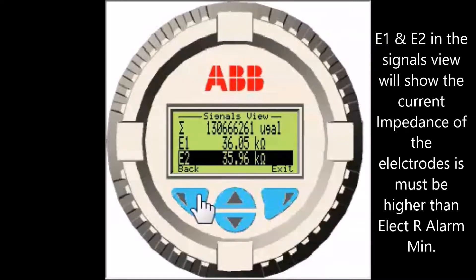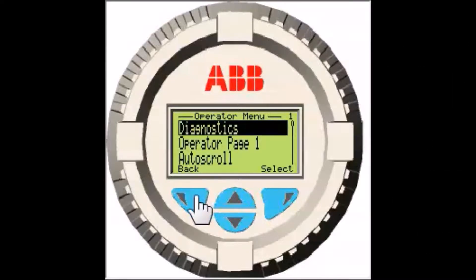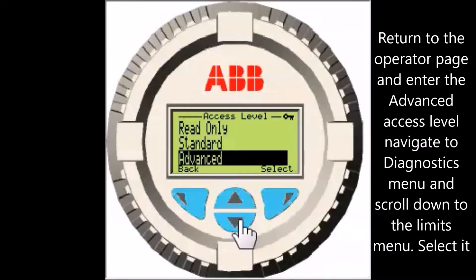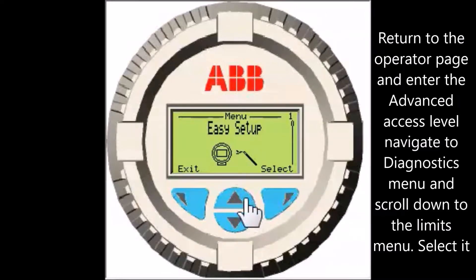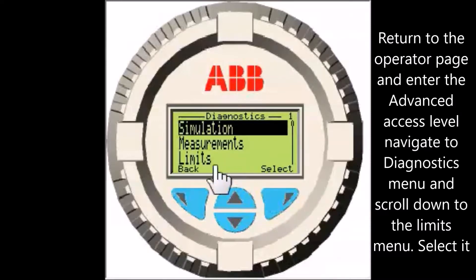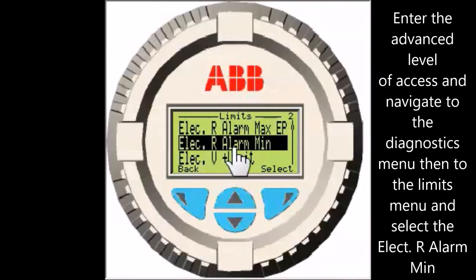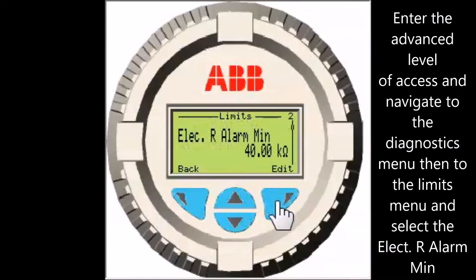Select the back soft key and return to the operator page. Return to the operating page and select the right soft key and scroll down to the advance access level and select it. Navigate to the Diagnostics menu, scroll down to the Limits menu and select it. Scroll down to the Elec. R Alarm Min setting and select it. The current electrode impedance limit setting is displayed.